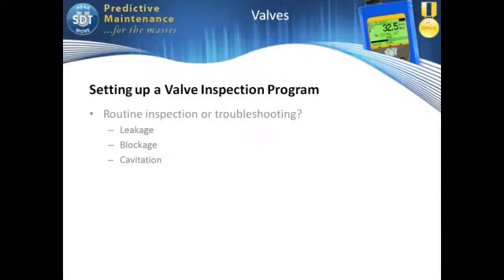Well, with my ultrasound system, I can look at 3 different aspects of my valve condition. I can look at leakage. I can look to see if my valve is passing. I can inspect a valve to see if it's blocked. And a third very big killer of valves around the world is cavitation. Cavitation kills so many valves, especially automated systems. When you have automated systems where a valve is opening and closing and there's nobody around, nobody knows it's screaming its head off due to cavitation. And it just fails prematurely. And nobody's taking care of it. So the amount of money that I can save in terms of valve inspection could be vast, absolutely huge.